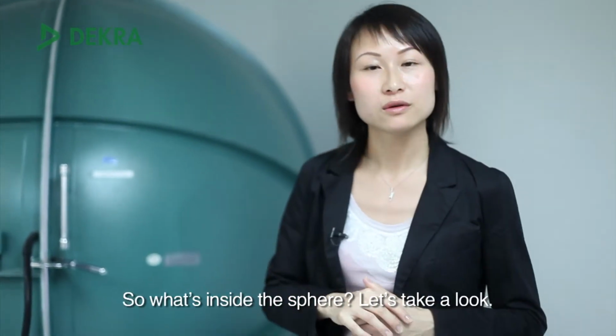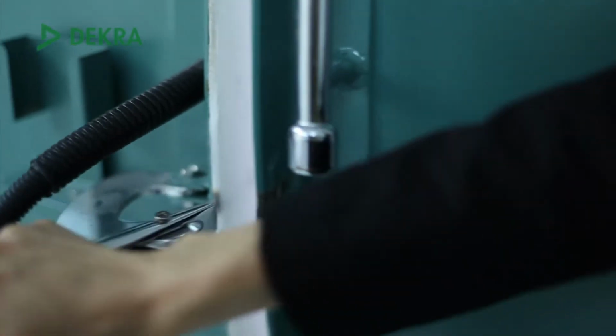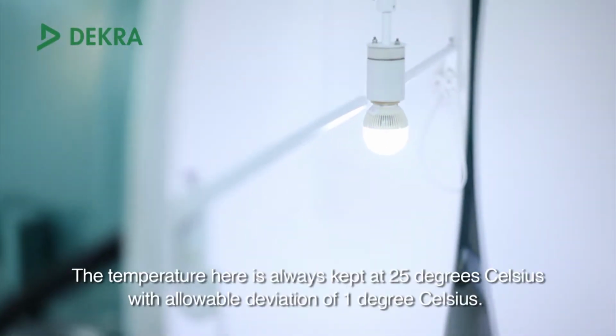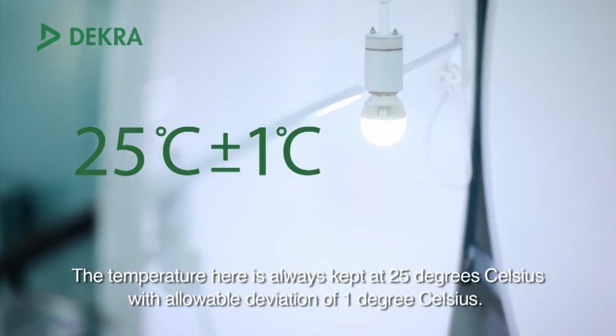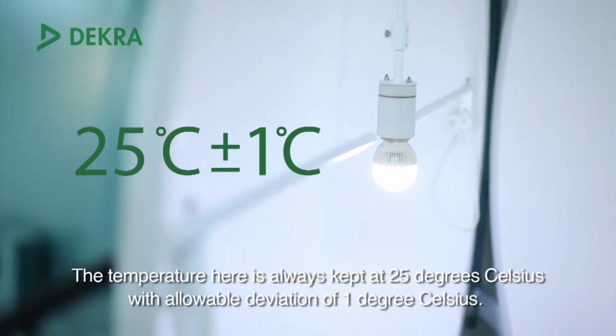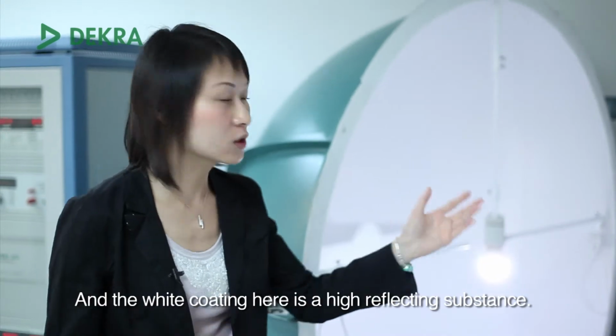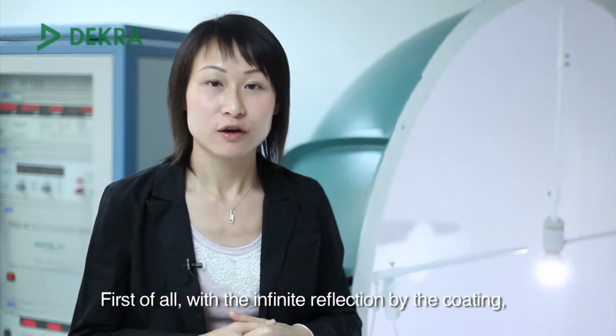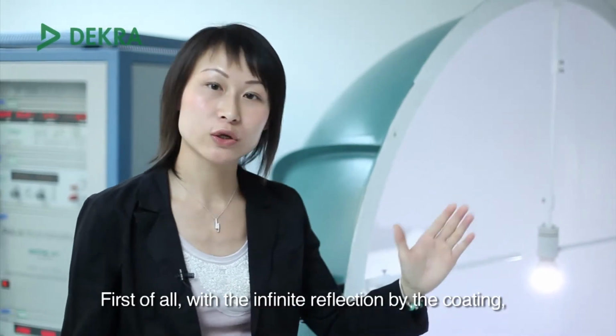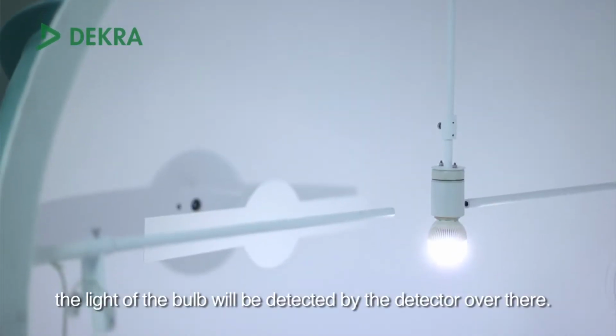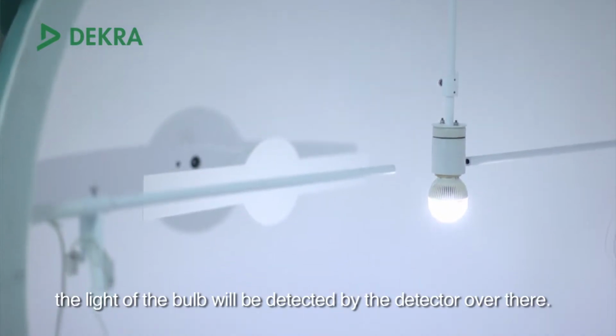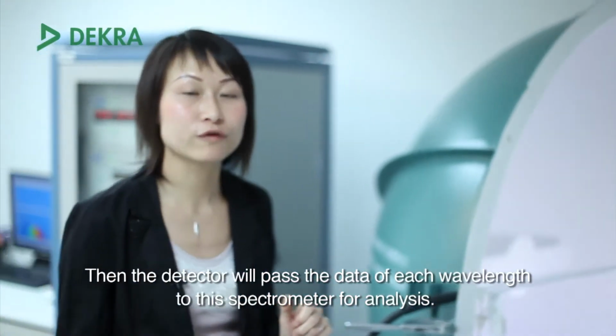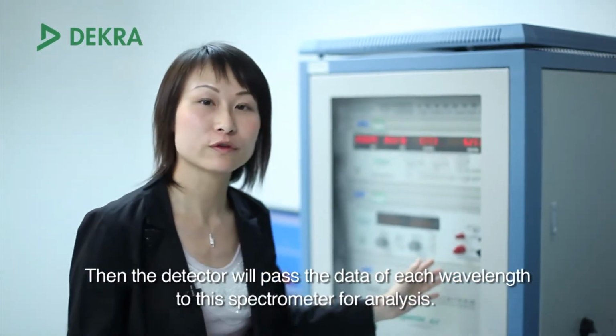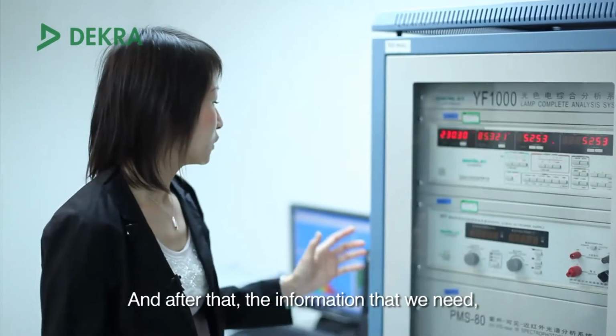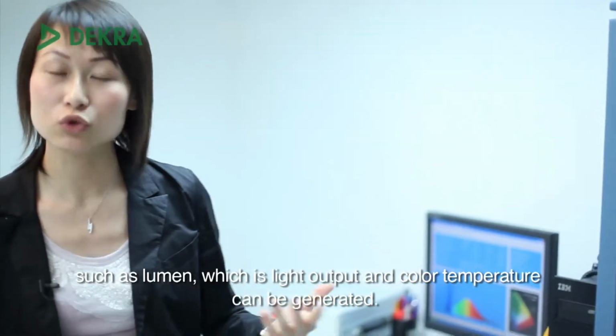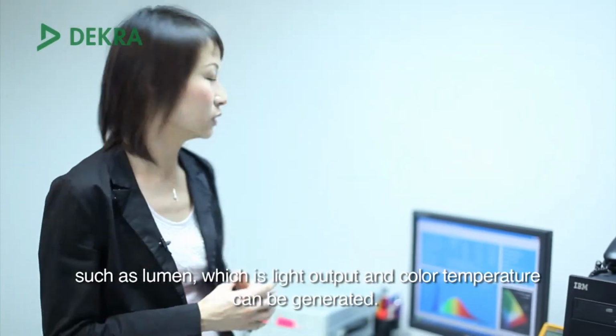So what's inside the sphere? Let's take a look. The temperature here is always kept at 25 degrees Celsius with allowable deviation of 1 degree Celsius. And the white coating here is a high reflecting substance. First of all, with infinite reflection by the coating, the light of the bulb will be detected by the detector over there. Then the detector will pass the data of each wavelength to this spectrometer for analysis. And after that, the information that we need, such as lumen, which is light output, and color temperature, can be generated.